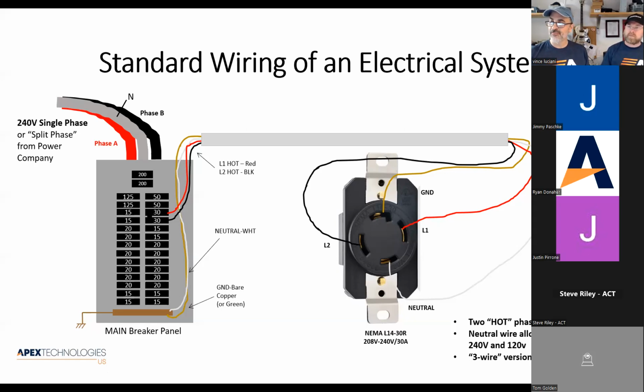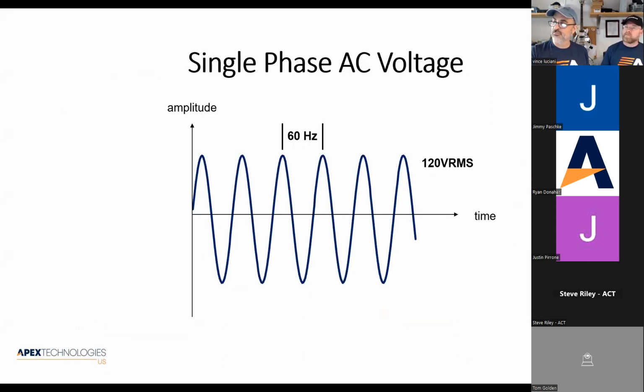If you have a really low end dryer that is just a turn knob and only uses 240 volts, there's no reason to have that other wire. But if you have an electronic dryer that has an LCD panel on it, most likely it'll be a 4-wire. So anyway, not completely important, just for completeness.